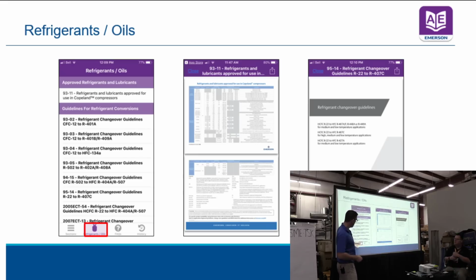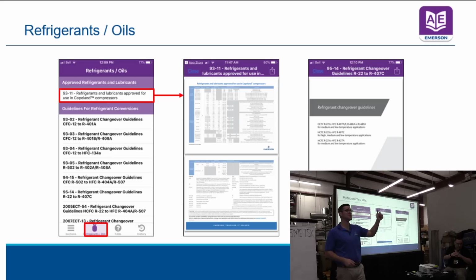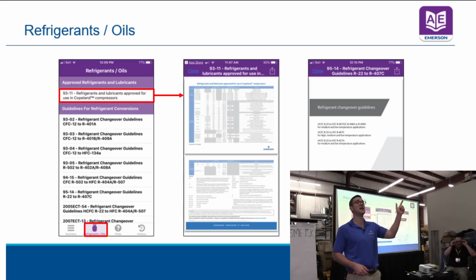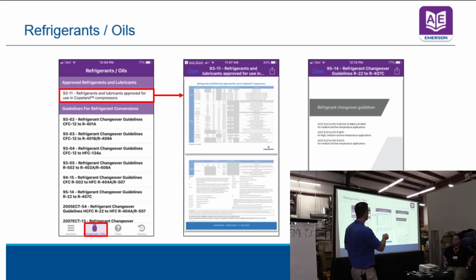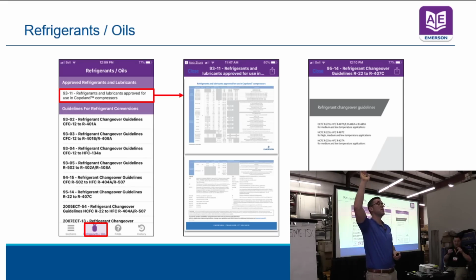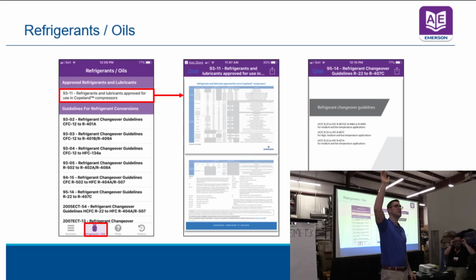Next tab down below here, refrigerants and oils. This is the number one guide for Copeland. If you're installing Copeland, you need to understand what oil goes in it and what refrigerant's allowed in it that we approve. So you go to this refrigerant 9311. How many people have heard of the 9311 bulletin? How many people install Copeland compressors? Show of hands. That's good. I like the hands going up there.